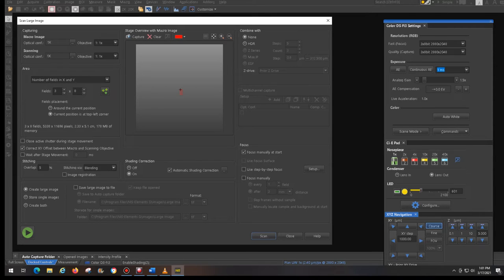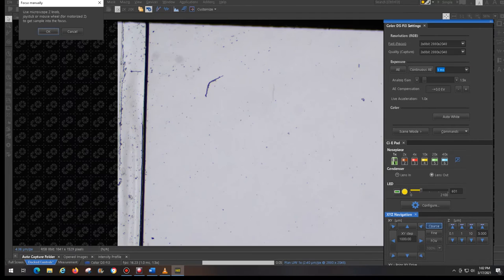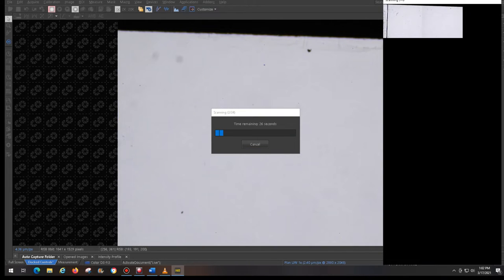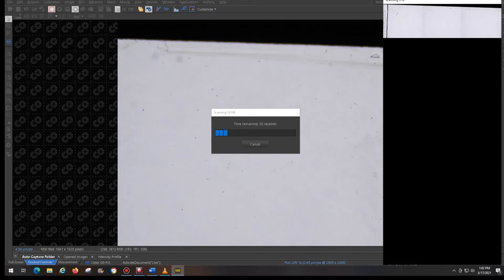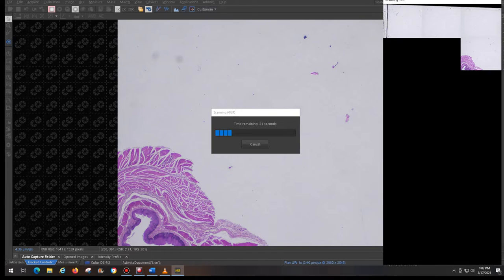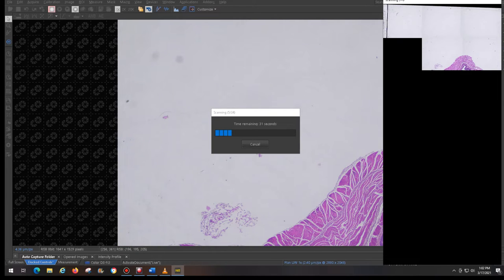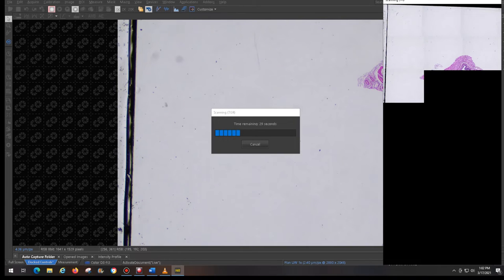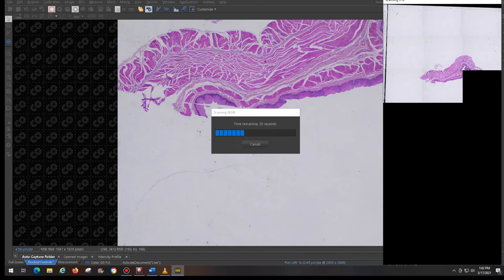The Ci-E can also be employed as a full slide scanner. One of the goals Nikon achieved when transitioning to infinity-corrected optics was the expansion of the magnification range available to the user. The new formula made the manufacture of a 1x lens possible. A 1x lens yields a larger field of view and reduces the number of fields needed to cover an area when compared to the 1.25 or 1.6x lenses available from other manufacturers.